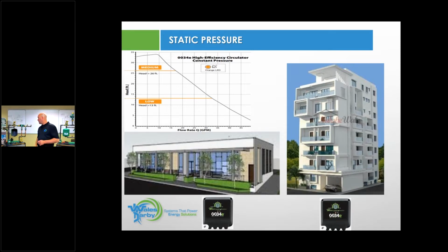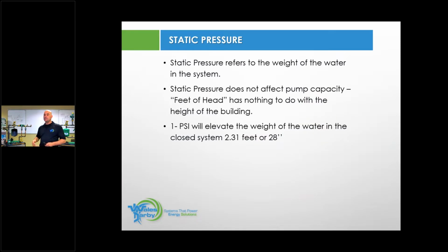So with that being said, static pressure refers to the weight of water in a system. Static pressure does not affect pump capacity, feet of head. So really that's the synopsis here. Does not affect it. 1 PSI elevates water in the system 2.3 feet or about 28 inches.